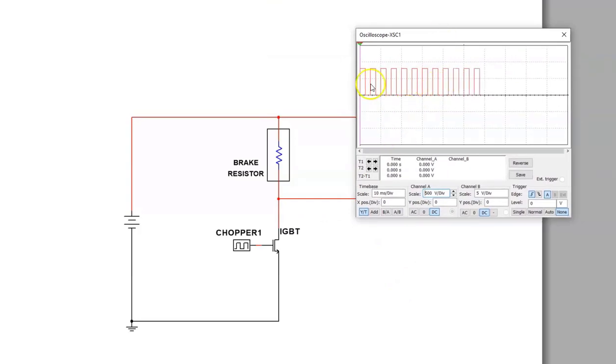What happens, and this happens very quickly, is this circuit turns on and sends out that extra DC bus energy to the braking resistor. And this is what is called DC pulse width modulation because it does not alternate below the zero line. It is just a straight DC.